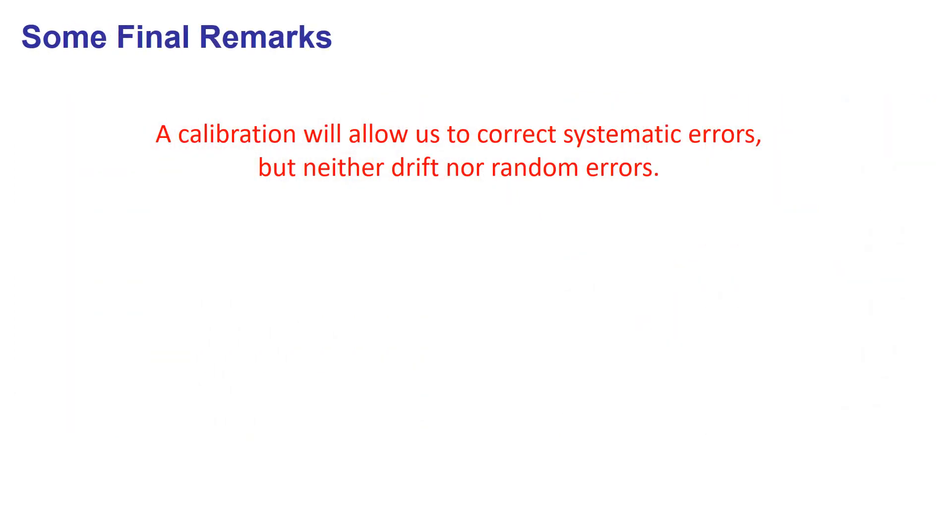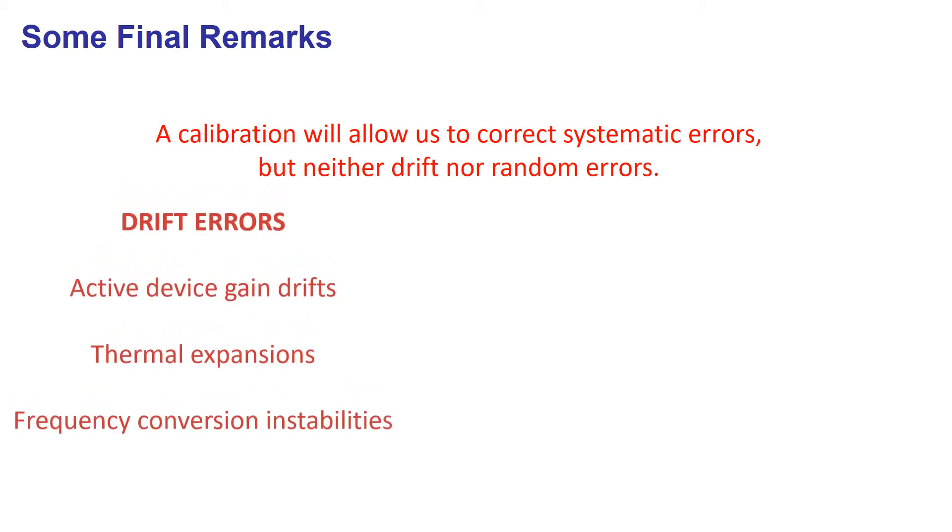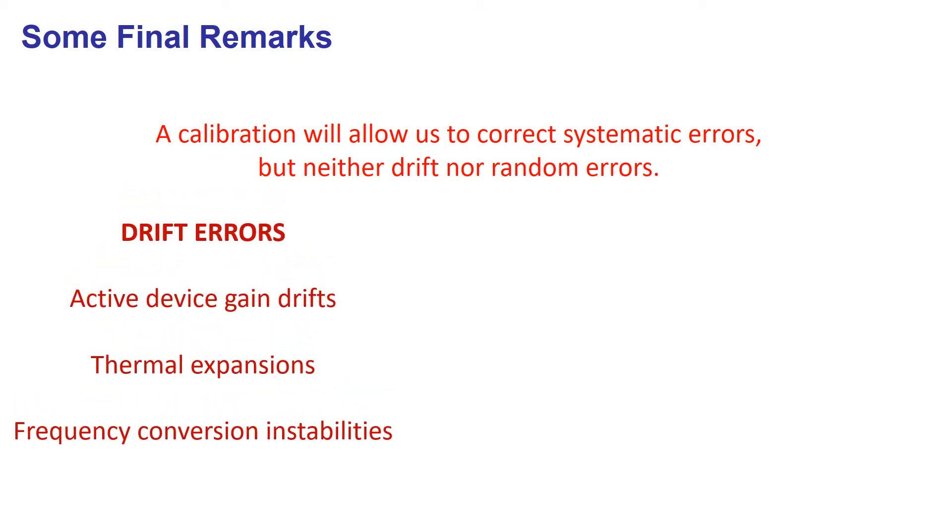Only systematic errors can be corrected with calibration. Other errors related to drifts and noise will remain. Drift errors might come from active device gain drifts, thermal expansion of cables, or frequency conversion instabilities of mixers.